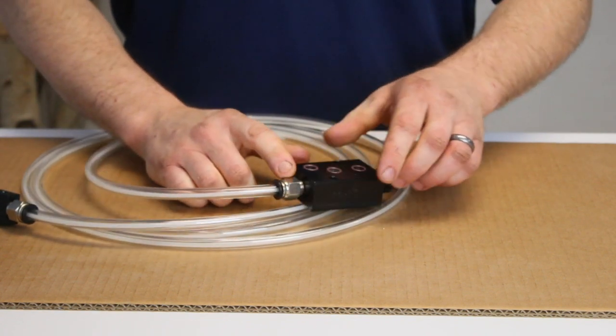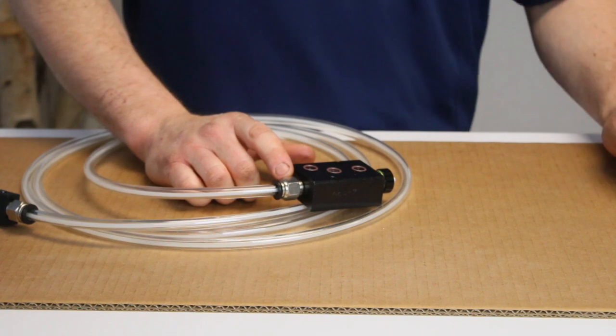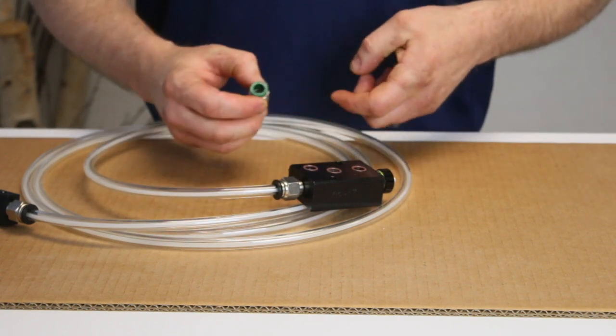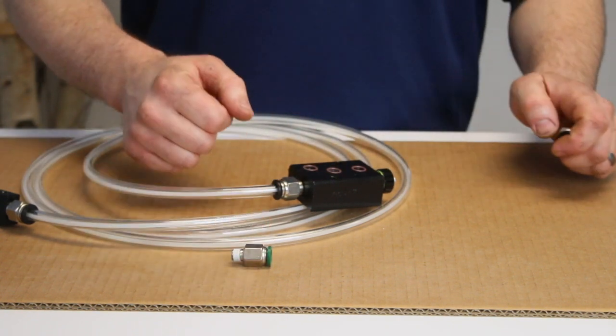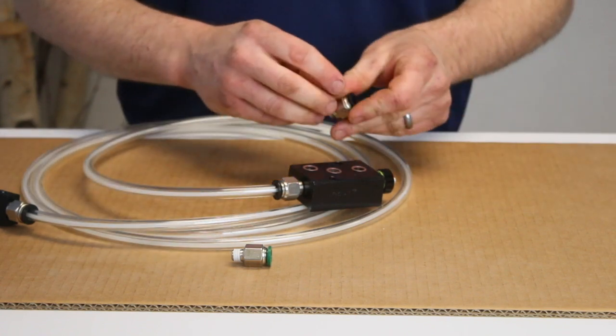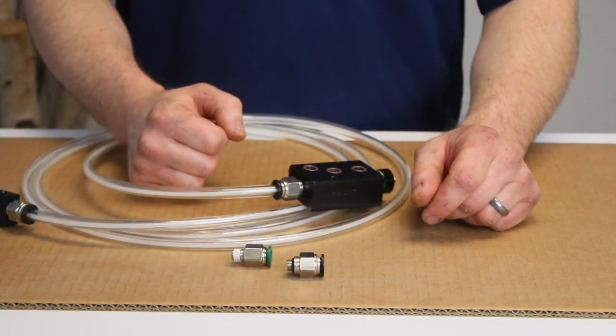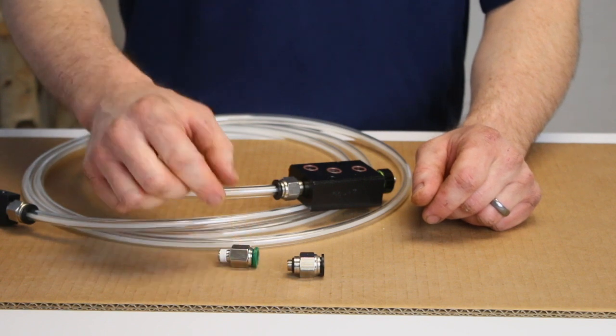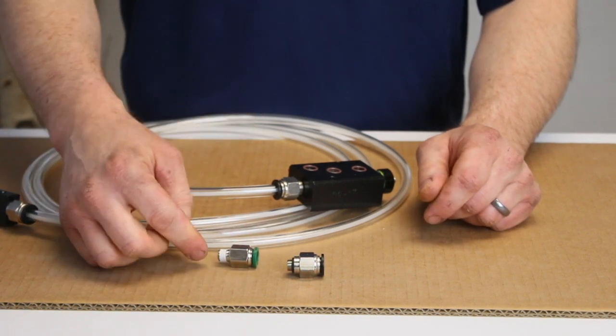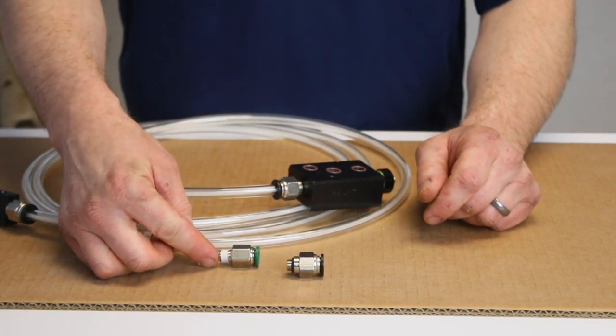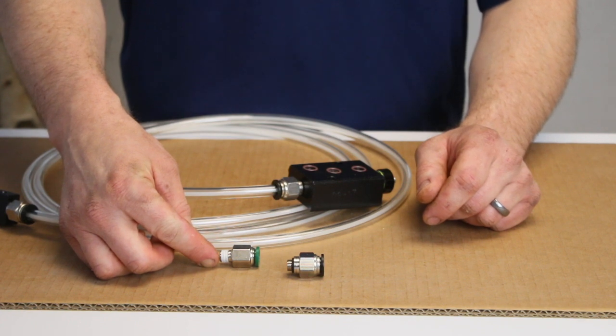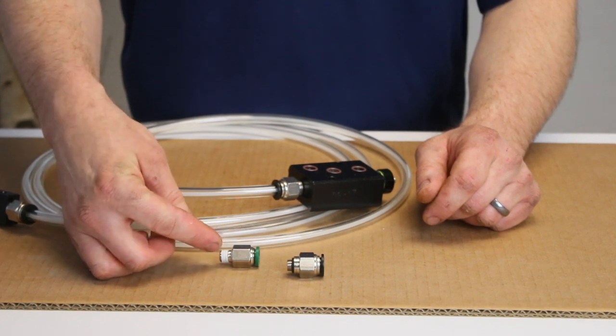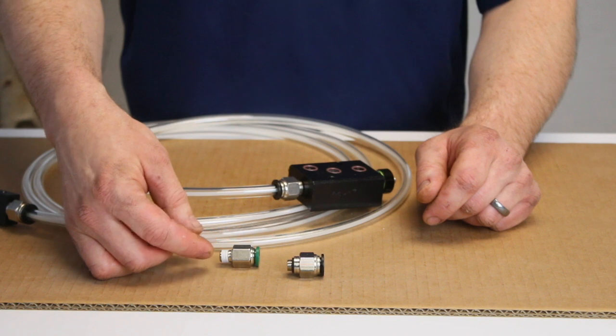Please note that there may be two different style push-in fittings on your pump. One style may have a green or silver release ring. The other may have a black release ring. The green or silver push-in fitting will have regular pipe thread fittings on it. This will require more torque and also sealant on the threads to seal it properly against the pump body.